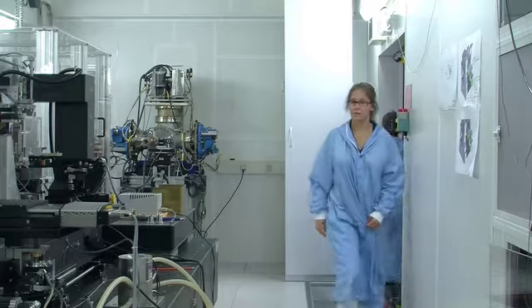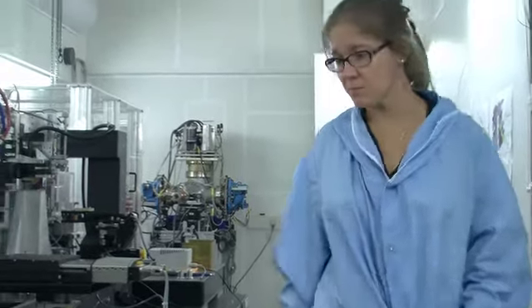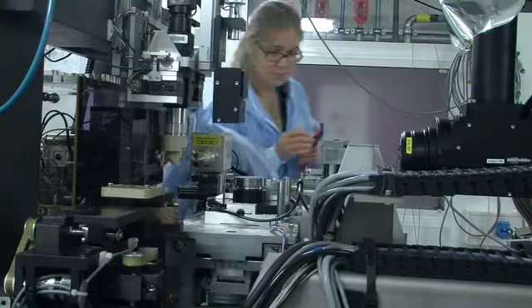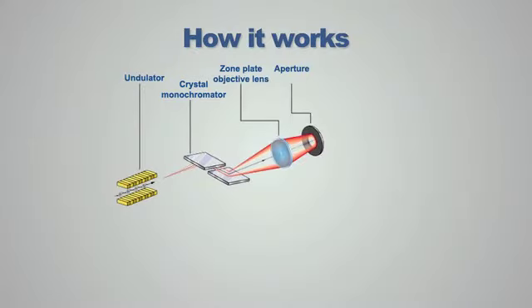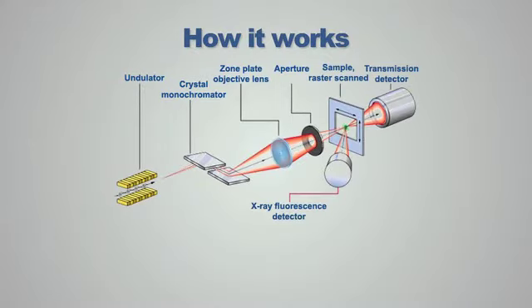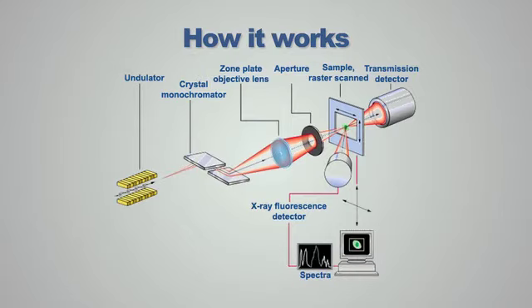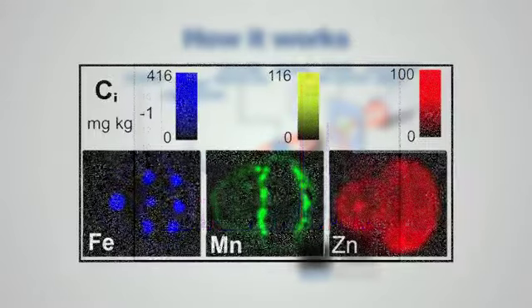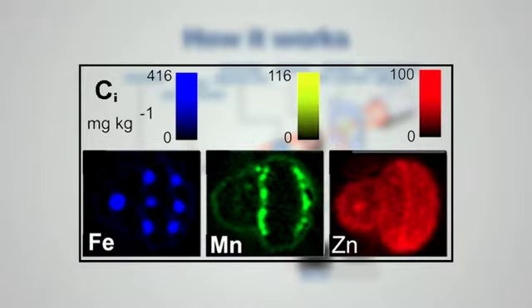The principle behind the technique is basically x-ray absorption. We collect the light as a secondary process of the x-ray absorption and we analyze it by energy — like this we are able to determine which elements are in the sample. The micro-x-ray fluorescent setup consists of three elements: the source, the focusing element, and the sample stage. We scan the sample in the beam and collect on a pixel-by-pixel basis each fluorescent spectrum for each point. From that spectrum, we build elemental maps with the composition of the different elements.